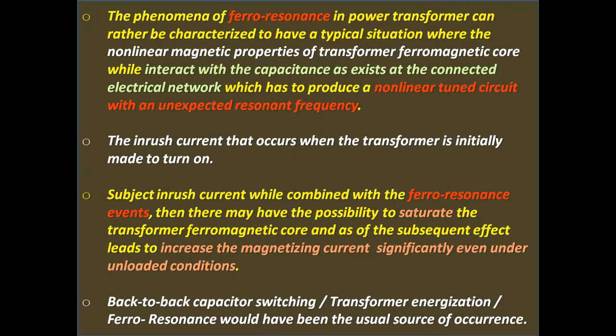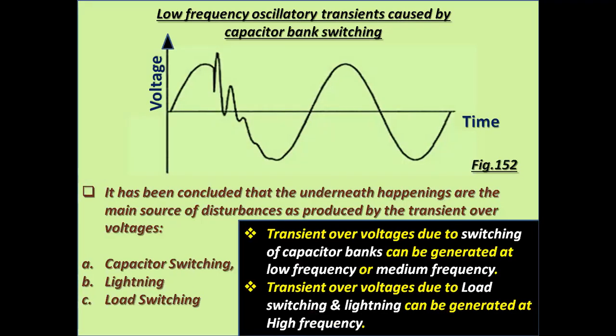The inrush current that occurs when the transformer is initially turned on, when combined with ferroresonance events, may saturate the transformer ferromagnetic core, and the subsequent effect is to increase the inrush current significantly even under unloaded conditions. Back-to-back capacitor switching, transformer energization, and ferroresonance are the usual sources of occurrence. Low frequency oscillatory transients caused by capacitor bank switching.